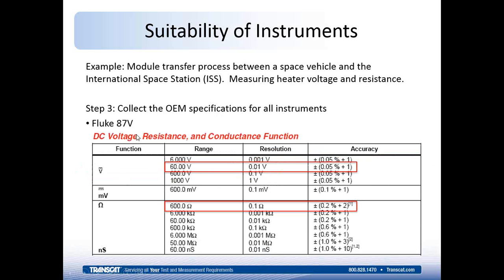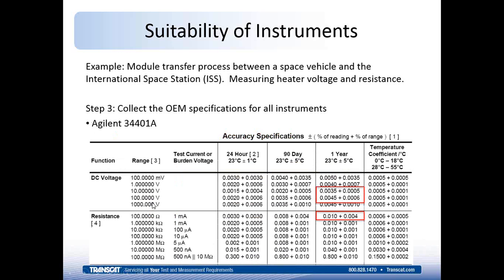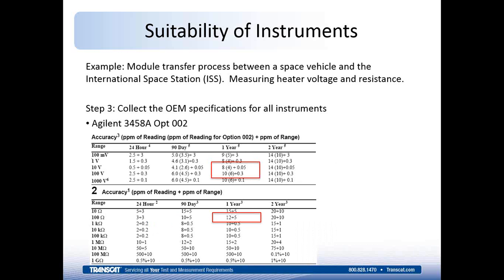The Fluke 87 was the second one in the list. It has a 60 volt range that will cover the 3 voltages we need to measure, and the 600 ohm range that will cover the 1 resistance range that needs to be measured. So it also is good, so far, for the application, just from a parameter standpoint. Same with the 34401, the 10 volt and 100 volt ranges can be used, as well as the 100 ohm range for the measurements. And finally, the Agilent 3458, which is a long-scale DMM, has a 10 volt and 100 volt range that can be used for the voltage measurements, and 100 ohm range for the 57.7 ohm resistance measurement. So those 4 instruments that we're considering cover the parameters that we need to measure.